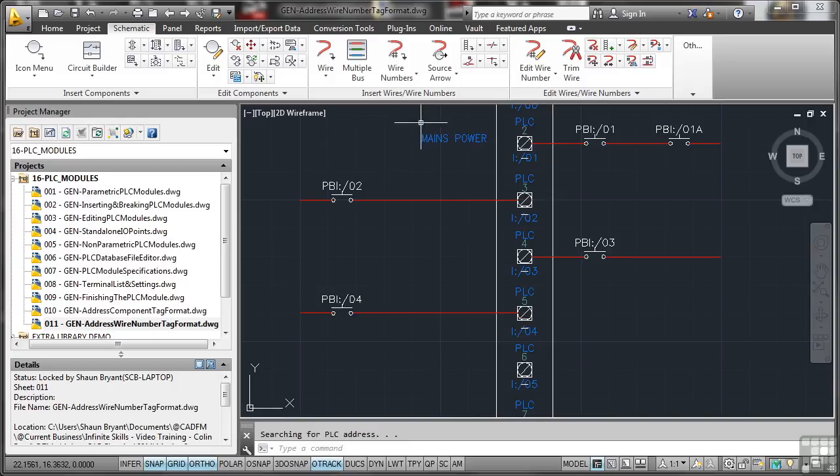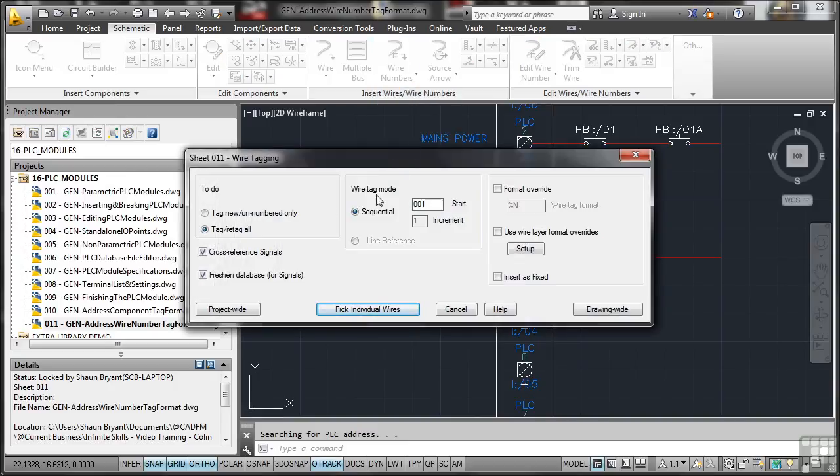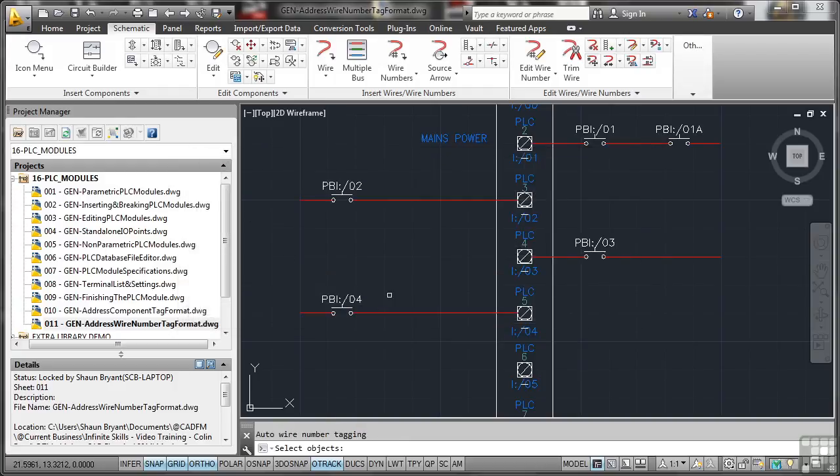So if I now go to wire numbering and I want to tag retag all sequential 001, I've already set it up in the project to pick up the input output address. So I don't need to think about it. There's the sequential start. I'm going to pick individual wires. If I pick that wire there like that and that wire there like that and press enter.